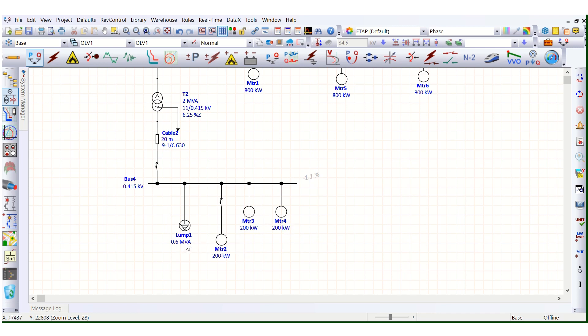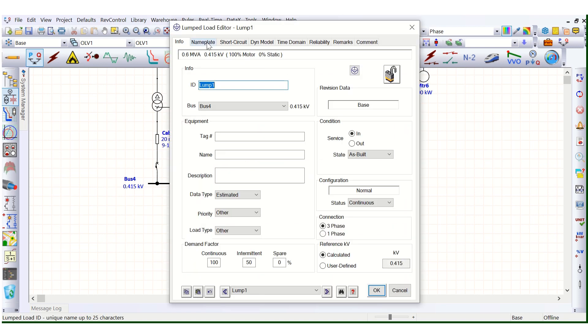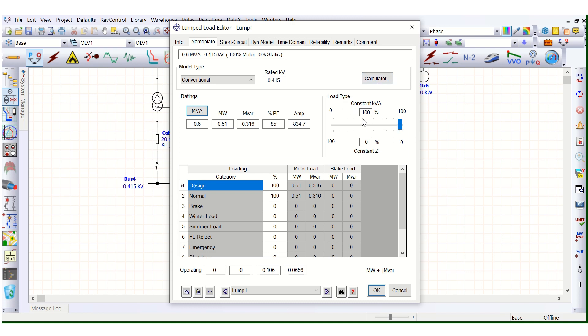Additionally, three numbers of 200 kW motors are connected, meaning 600 kW plus 0.6 MVA load is connected to the bus. Sometimes if the switchgear or connected bus is overloaded, ETAP will throw this error message. This lump load is a constant power load — 100% motor load — with 0.6 MVA, giving reactive and active power at 85% power factor.